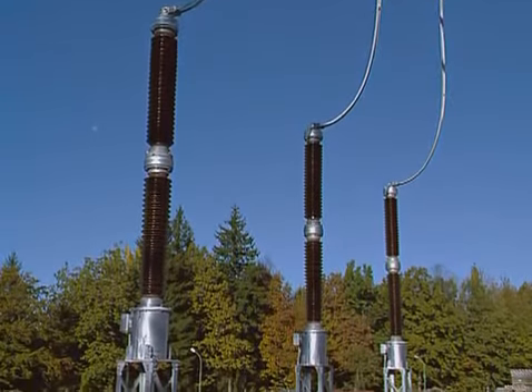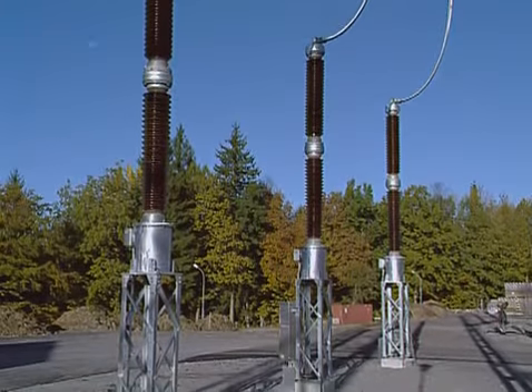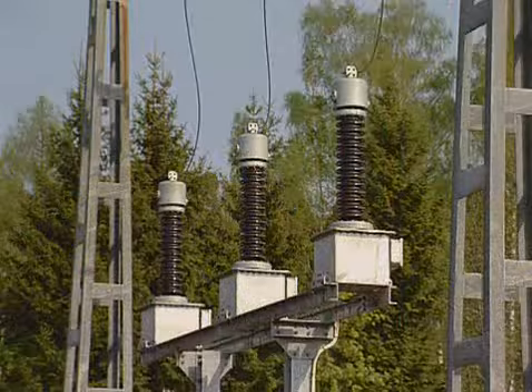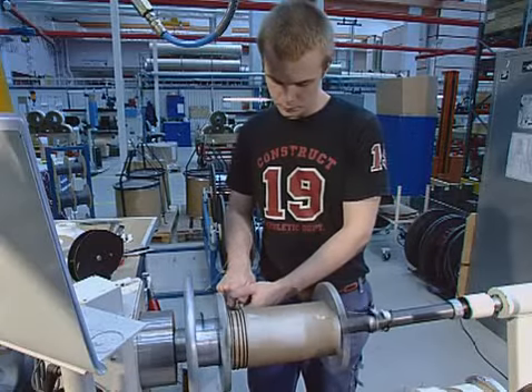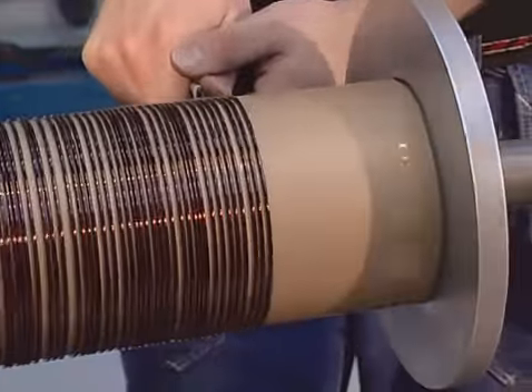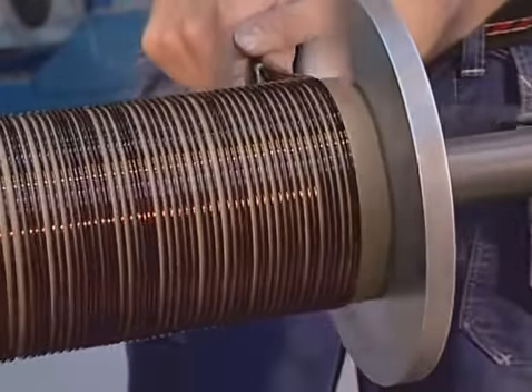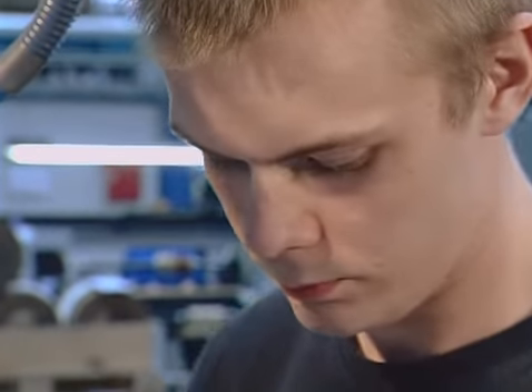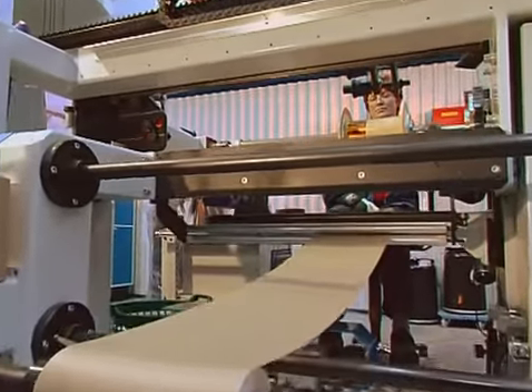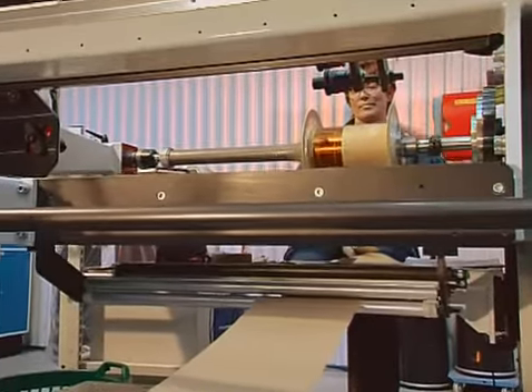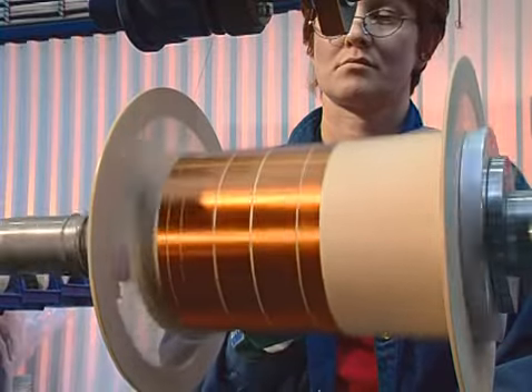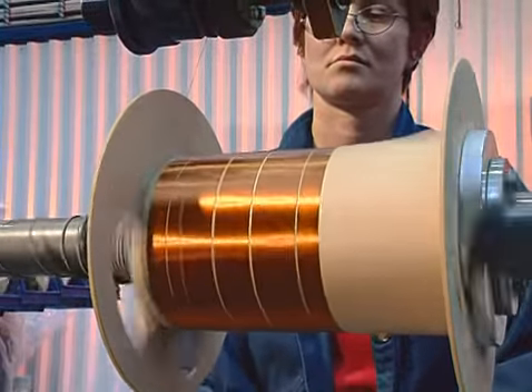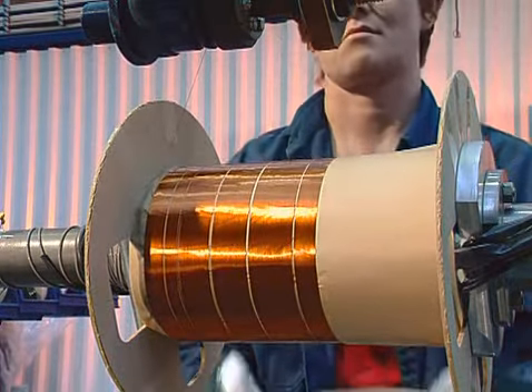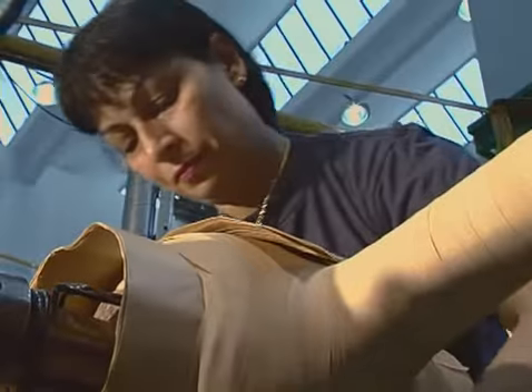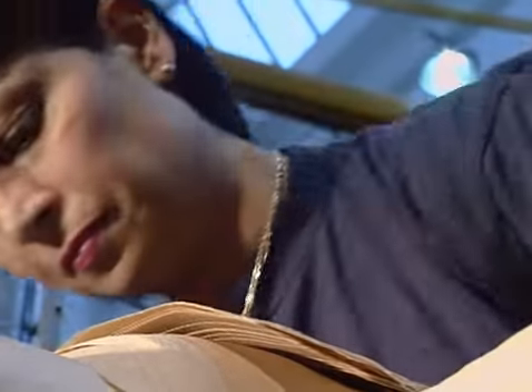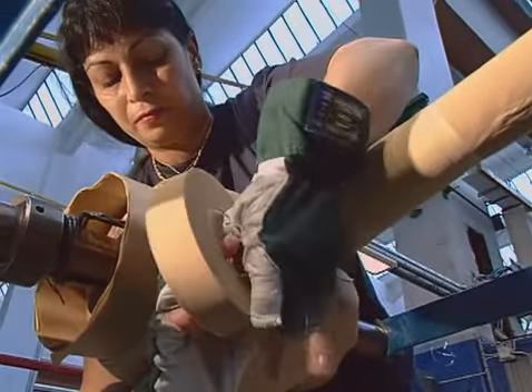The low voltage and high voltage windings of the inductive part, in both the capacitor and inductive voltage transformers, are constructed in the same way. The low voltage windings consist of only approximately 100 turns, but the high voltage windings are wound with a very thin wire, up to 50,000 turns. A sheet of paper insulation is laid between every layer. The inductive part and its high voltage connections are then insulated with paper.